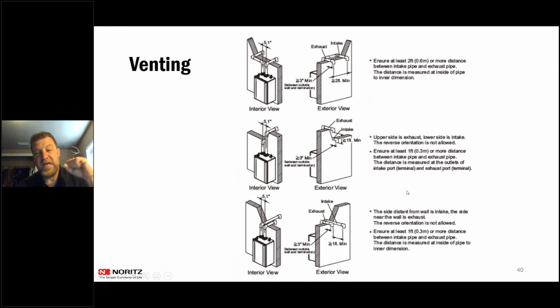Alrighty. So the actual vent of one of our units coming out, every manufacturer has a different way of what they say they need to have going out. So with our easy units, this is out of our easy book here. If you're bringing 2 pipes out and you're on the same level coming out of the house, they want to make sure that that intake is 2 feet away from that exhaust. But if you're offsetting, whether you have one above or one below, it only is a 12-inch separation between those two. So if you're coming out of the house and you're dropping your exhaust right next to the house and then taking your intake out another 12 inches and then dropping it, you have that 1 foot minimum.